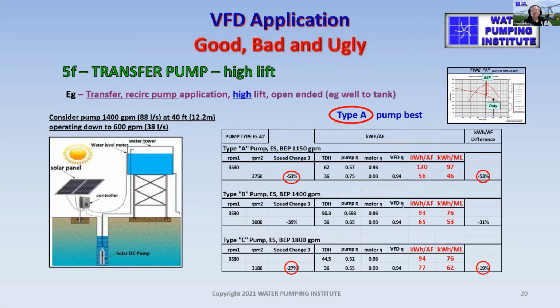And then we go to pump B, and it's less, but pump C, type C, the speed change only required 27%, but it only saved 19% in energy. So pretty much, there's your type A pump, gets the big tick for this type of application, and type B pump bad, and type C actually quite ugly. Didn't really save that much energy at all.